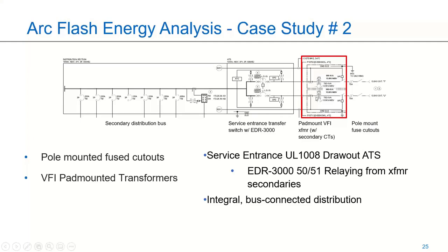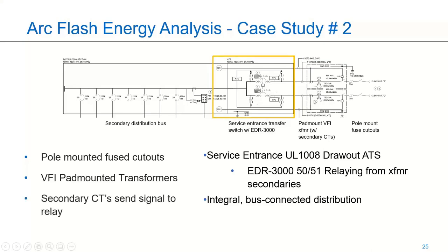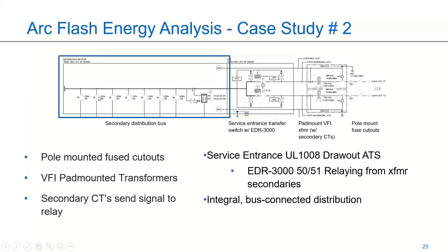I talked about on-site commissioning. There's still a little bit to tie here. This is not a fully integrated package, but it is getting a little bit closer and consolidating those components, allowing the factory to functionally verify this whole component rather than a separate recloser, separate transformer, separate relay. We're getting a little bit more integrated here. And then the rest of the feeder bus, which is somewhat ancillary in this discussion.